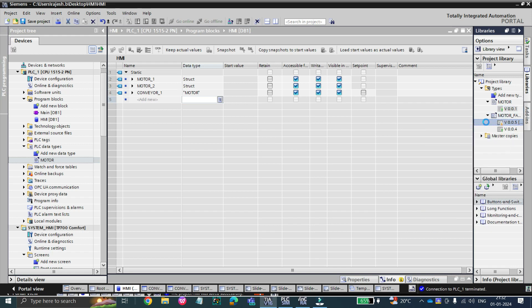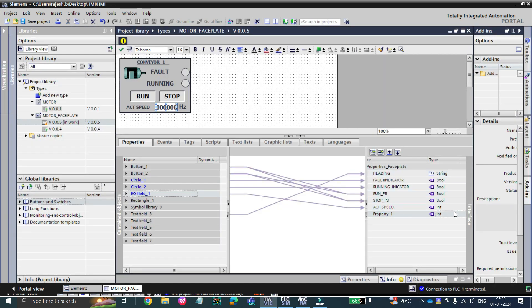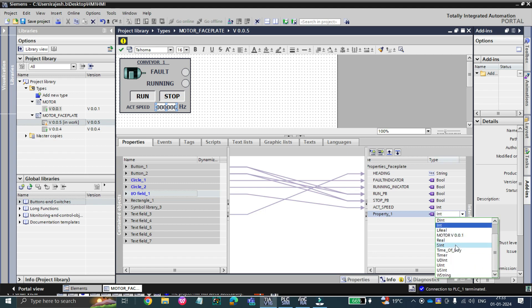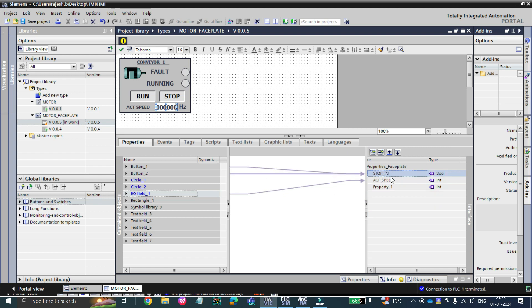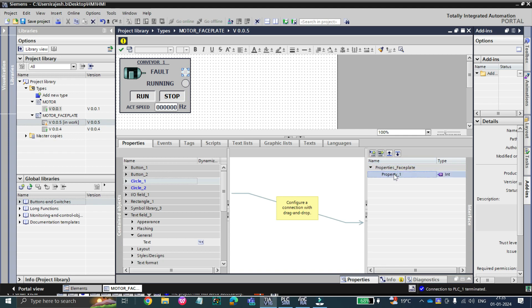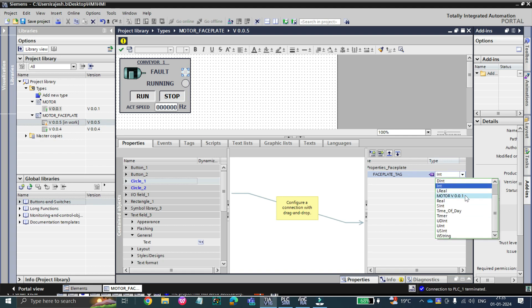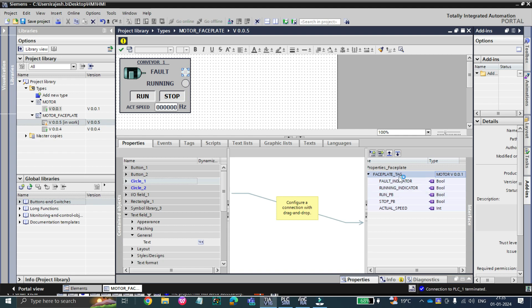Let's see if we can view the data type in our faceplate work window as well. By double-clicking on it, you can see motor version 0.0.1 is now showing. We will delete all the current properties. Now add another tag, give it the name 'faceplate tag', and at the type choose motor version 0.0.1. You can see that all the values from the motor data type are now showing.